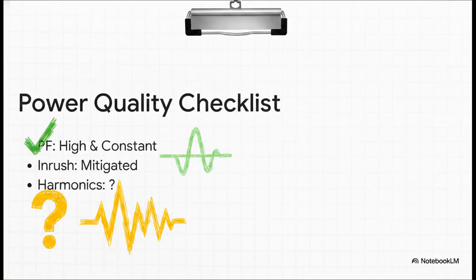Just a really quick recap of our checklist to set the stage. We've already completely solved the reactive power issue. Modern AC VSDs inherently hold a high and constant power factor across all motor speeds. Check. We've also tamed that nasty inrush current because the drive gives us a nice controlled soft start instead of slamming the grid. Check. So that leaves us with the trickier challenge, the one with the question mark. Harmonics. It's the one that really gets engineers arguing, and it's exactly why upstream design decisions matter so much.